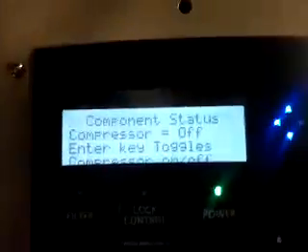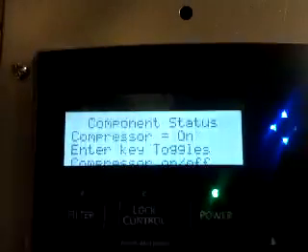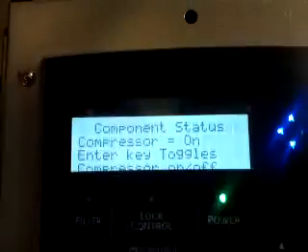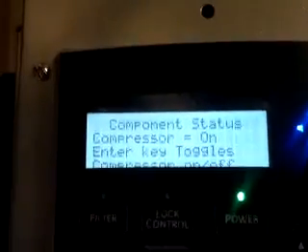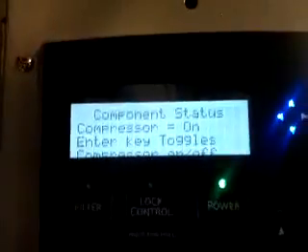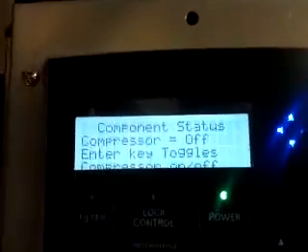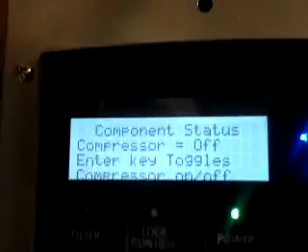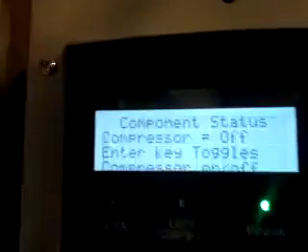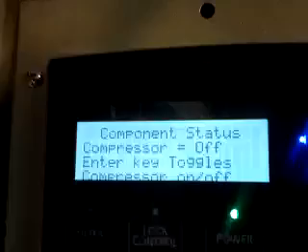You can also key on the compressor — press Enter and you can hear it kick on. However, you don't hear the fan because this is a test mode. Don't run the compressor this way for more than one or two minutes, because beyond that the head pressure on the high side will get too high and cause permanent damage to the unit.